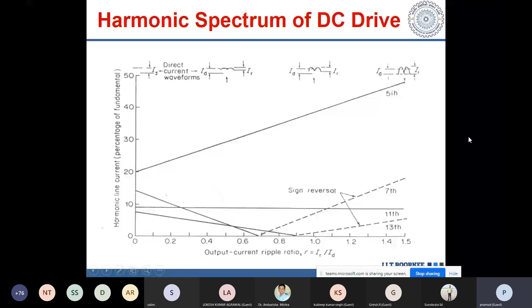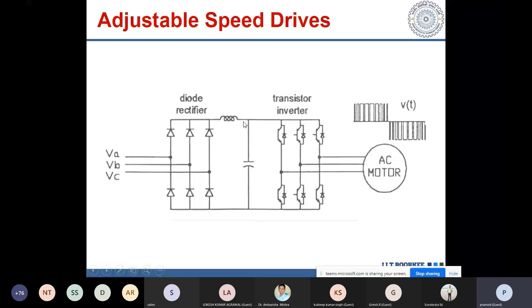You can also have an adjustable speed drive, one of the major applications in today's time, where we have an uncontrolled diode bridge rectifier, and then you have the inverter. Now this diode bridge rectifier will draw current from the supply depending upon the load requirement. Maybe it is a pulse current like this. Whenever the capacitor voltage falls below the line-to-line voltage, a current will be drawn. So there may be two current pulses in half cycle. And if you do the harmonic spectrum, it has fundamental, fifth, seventh, and other odd harmonics may be present other than triplens.